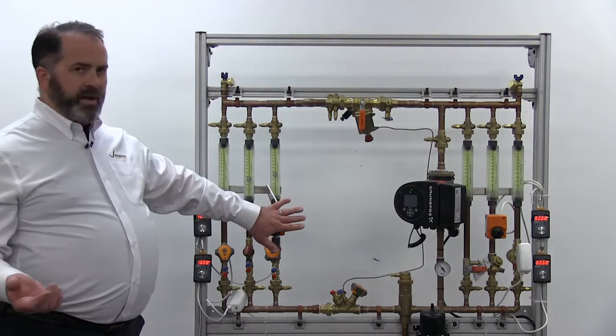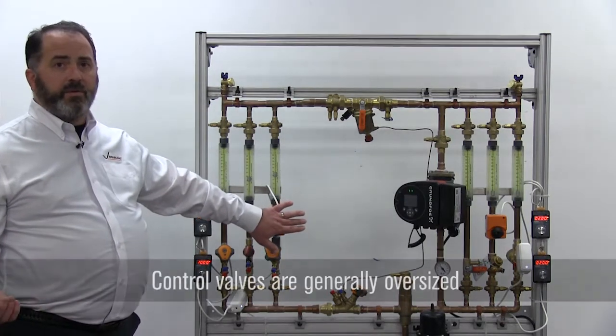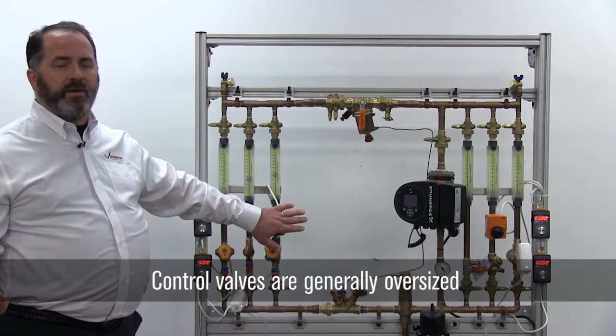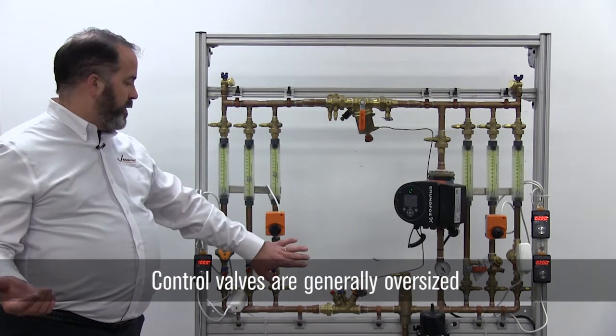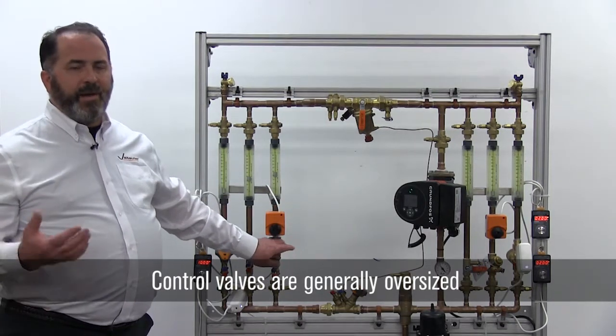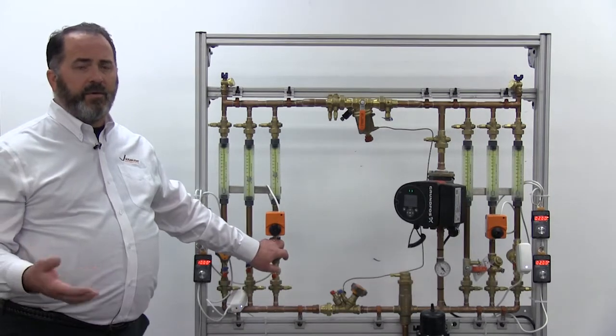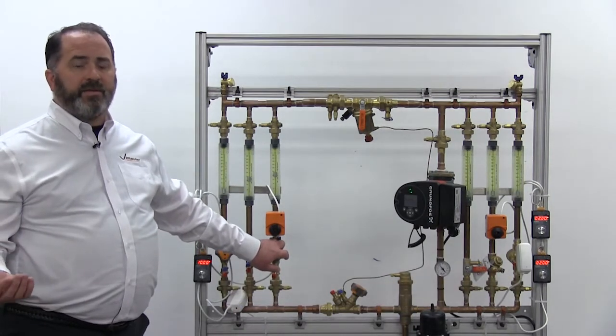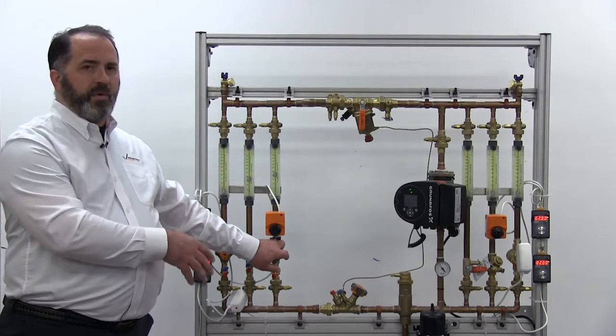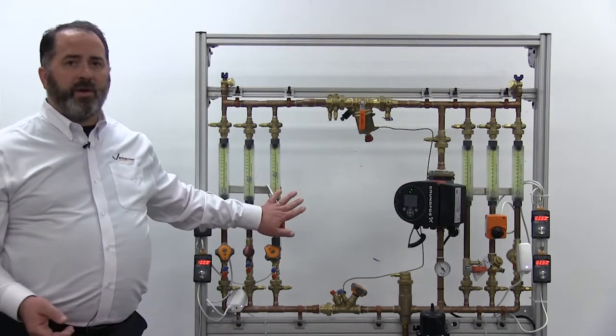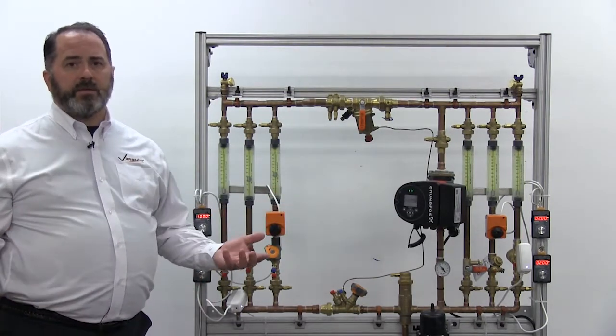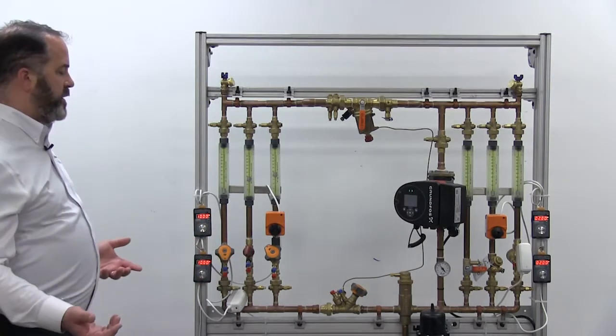In order to get the control they need, they'll tend to oversize the control valve because then they know they'll be able to get the available flow through it. And then you're making the problem even worse because now you have to throttle. Since you have an oversize control valve, you have to throttle back on the balancing valve even further, giving that balancing valve even more authority and taking more authority away from the control valve. Again, you're making the system worse by doing a one size fits all.